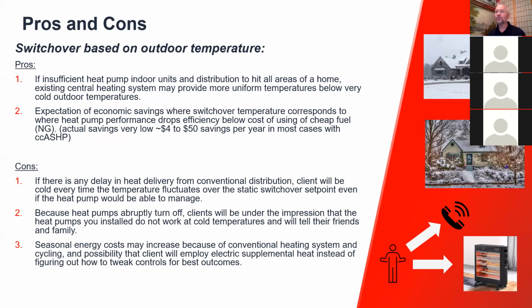So the cons, the reasons why switchover may not be totally great. One of them is comfort, right? And I'll get into some real close detail when we get to the end of the slide deck about an example of Massachusetts. But when you're switching between heating systems, there's a lag in the period of time it takes for a system to deliver heat. When you turn on a conventional heating system, the pipes or the radiant or whatever the delivery means is, takes a little while to catch up. And so, depending on that switchover temperature, you can have a comfort lag there. And that will give people the impression that there's something wrong with the system.